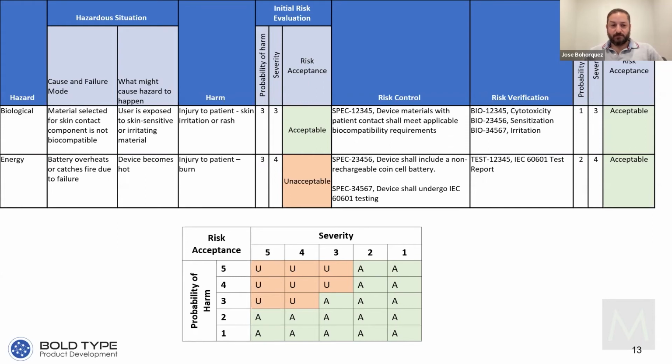Sometimes what makes more sense is to have a different line item in this that has a different severity and a different probability, because it might be that it's low probability that something happens and it's a higher severity, and maybe it's a higher probability that it happens, in a slightly different way or under different constraints and has a lower severity. And so it's better to break it up than to try to argue that your risk control changes the severity. So this is a very practical thing that surprised me when I was first doing this.